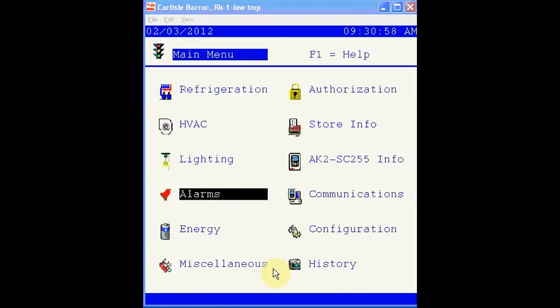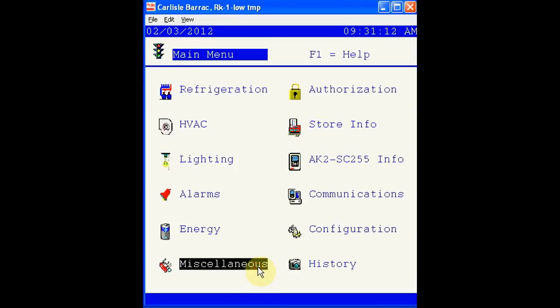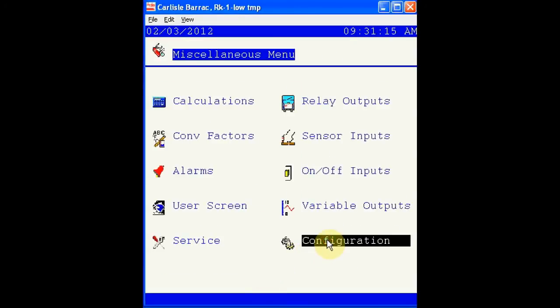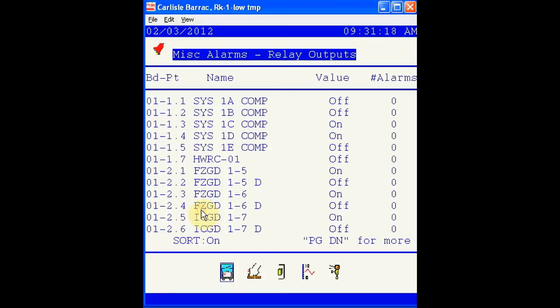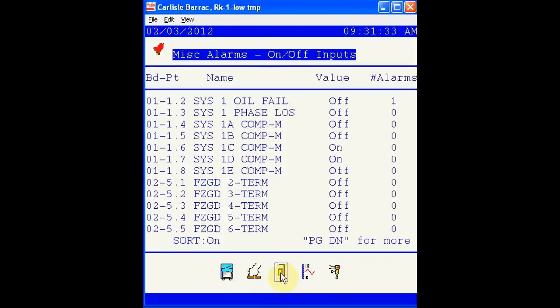Next, let's look at miscellaneous alarms. These may include individual points that don't fit the current conventions for alarms. To access miscellaneous alarms, you may view those through the alarm menu or through miscellaneous. Here you see the normal groupings for I/O points: relay outputs, sensor inputs, on-off inputs, variable outputs, and other controllers. Let's take a look at on-off inputs.